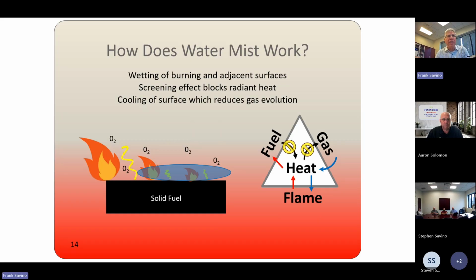Also, the wetting of adjacent surfaces. With water mist systems, despite what some people believe and what other people tell you, things do get wet, okay? So you can't think of water mist as like a clean agent where things are not going to get wet. Things are going to get wet with water mist, okay? So by wetting the adjacent surfaces, they're less likely to undergo their process of pyrolysis, all right? Because of the heat of vaporization required of the water when it coats that other burning material. Also, the water mist has a screening effect, so it's blocking the radiant heat so that adjacent surfaces are not subjected to the high heat of the fire. And also with the water mist, you're cooling the surface of what's burning to reduce the gas evolution or the pyrolysis.